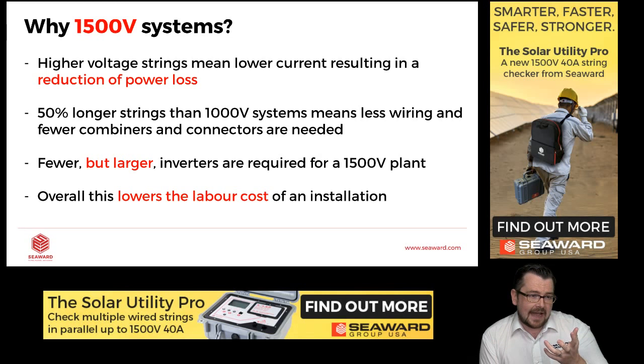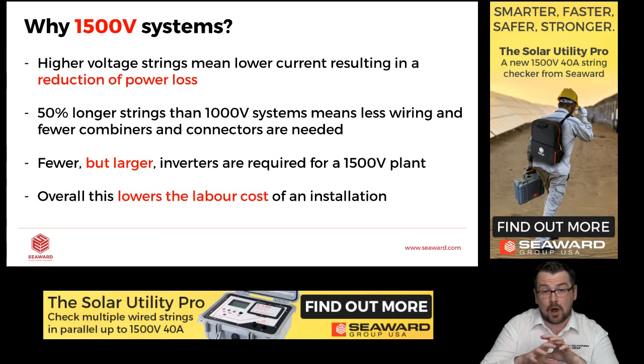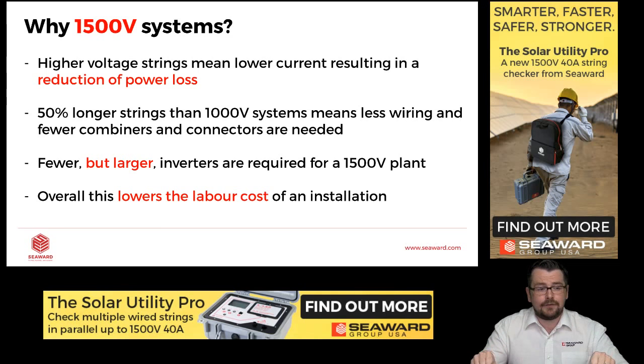Well, obviously, if we have higher voltage strings, this means we have a lower current. So this results in a reduction of power loss. Okay, so that means we're generating more power from longer strings. With 50% longer strings at 1500V than 1000V, this means we have a lot less wiring. There's less cable, fewer connections, fewer combiners are needed, and overall that really drives down the balance of system costs. So you can save a lot of money per kilowatt peak, and indeed per megawatt peak with a 1500V system.